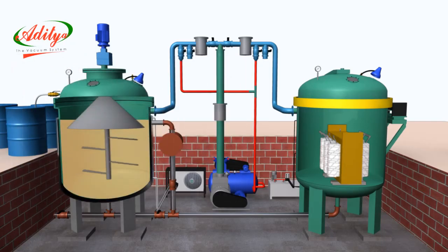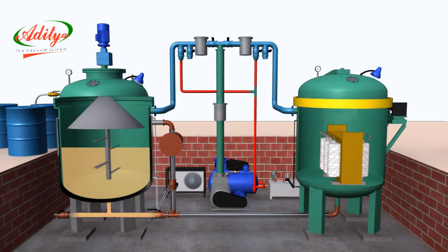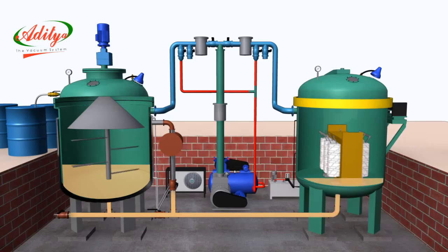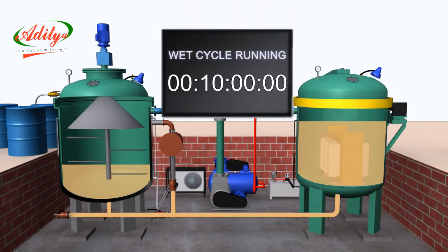The resin or varnish starts flowing from storage tank to impregnation tank. The operator needs to observe the resin or varnish level inside the impregnation tank through the glass window. Once it reaches the required level of resin or varnish, the loading will stop. After completion of varnish loading process, timer will start and maintain the required vacuum level inside the impregnation tank. During wet cycle process, the display screen indicates Wet cycle running.